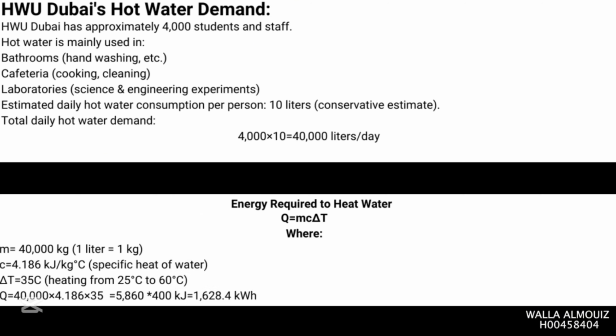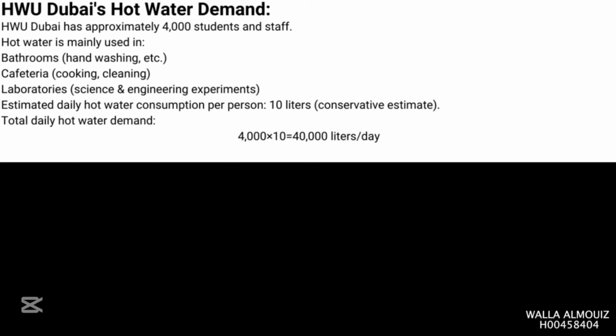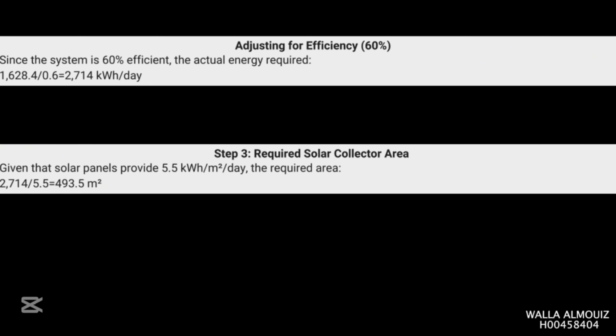To meet Heriot-Watt University Dubai's daily hot water demand of 40,000 liters, we calculated the energy required using the heat capacity of water. The result is approximately 1,628 kilowatt-hours per day. Considering a 60% efficiency rate, the actual energy needed rises to 2,714 kilowatt-hours per day.